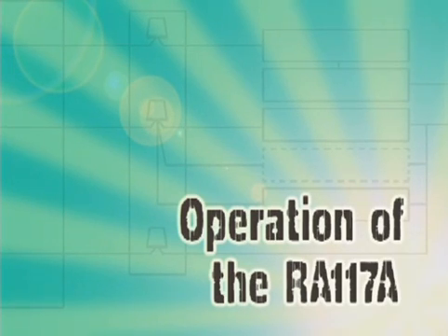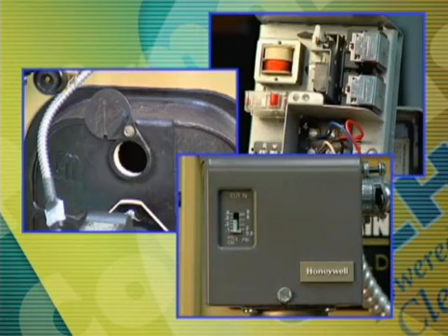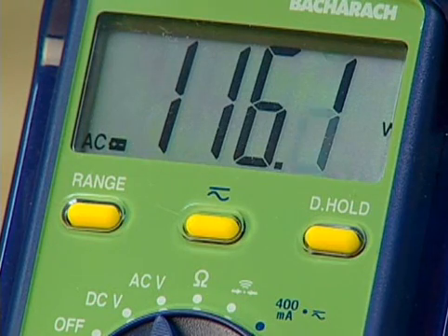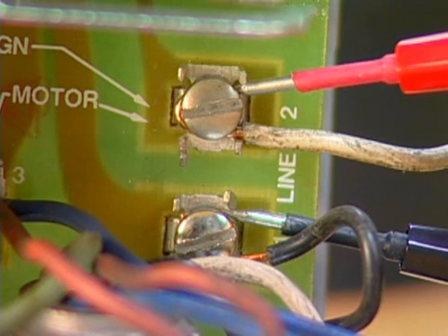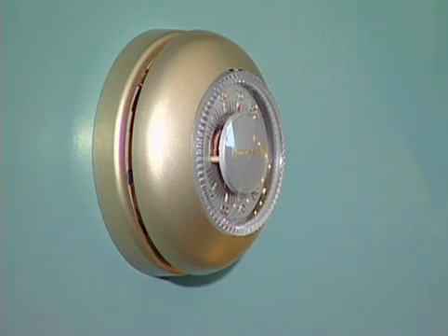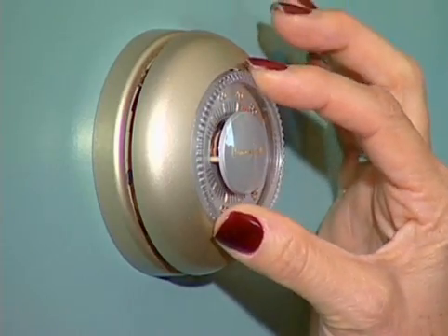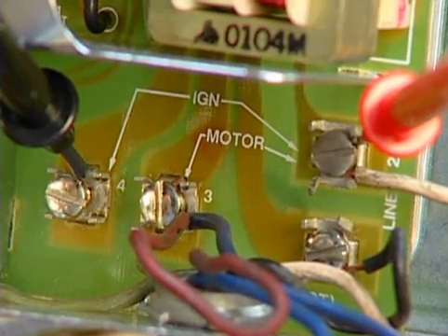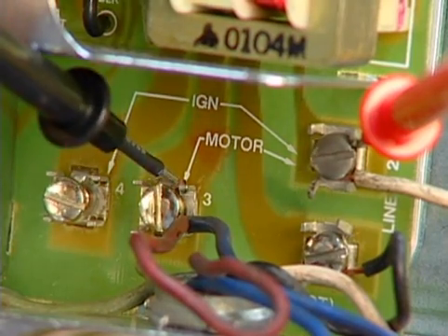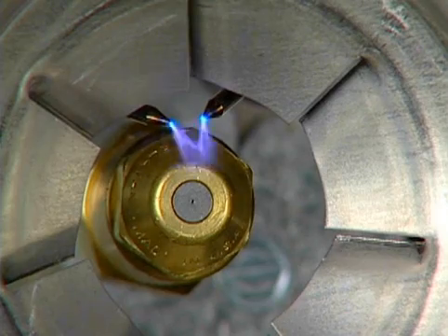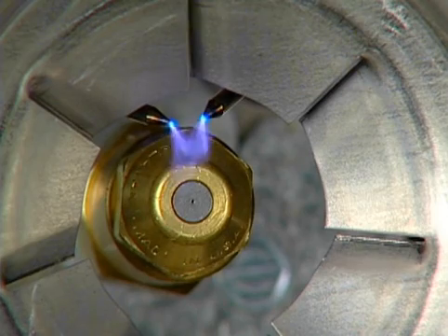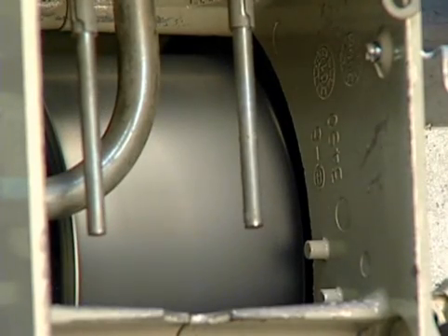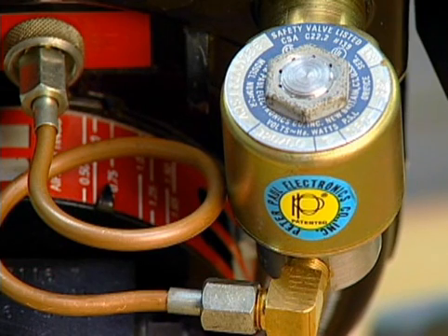For the next few minutes, we'll examine the operation of the RA117A. If all components are functioning properly, the control is in standby mode until line voltage is applied through the limit control to terminal 1, and a call for heat from the thermostat completes the circuit between W and B, or TT. Then terminal 4 will be powered, and terminal 3 will be powered a split second later. The transformer will generate ignition through the electrodes. The motor will turn the fuel pump and burner fan. If there's a delayed oil valve installed, it will open based on its delay timing.